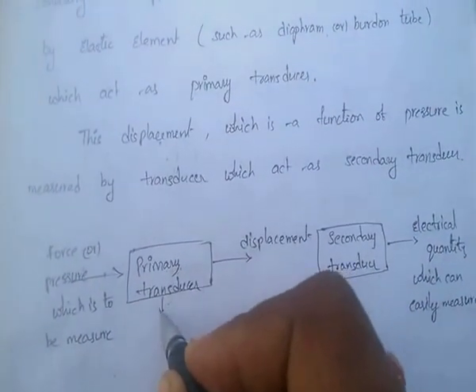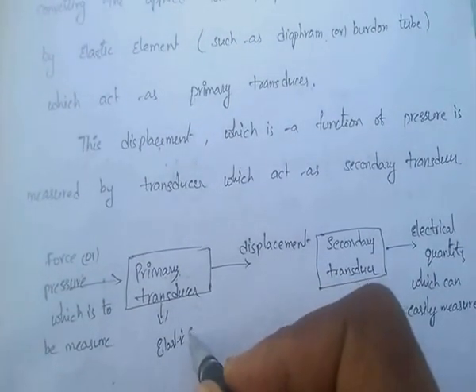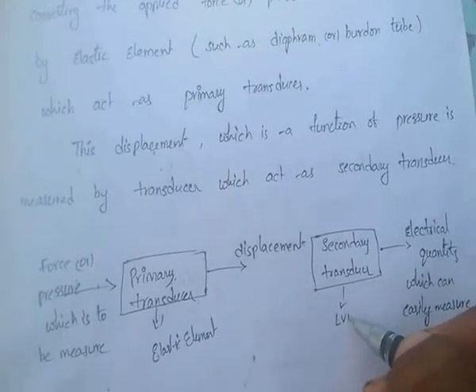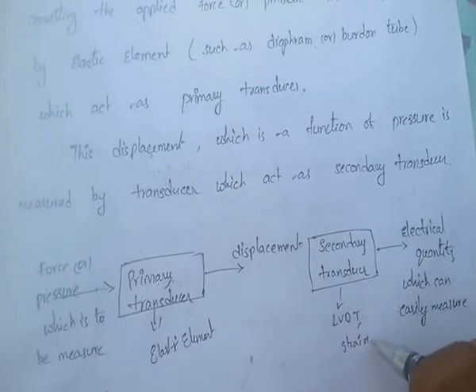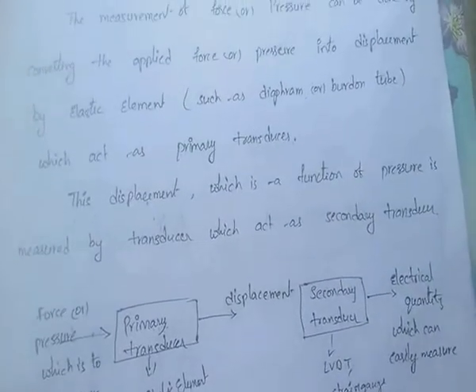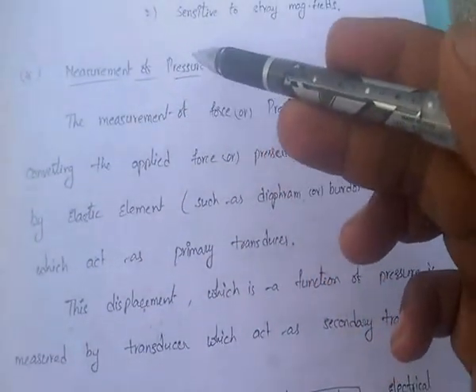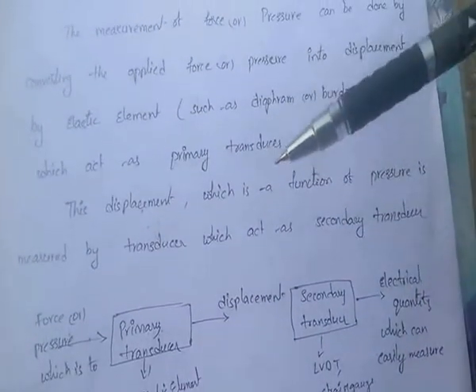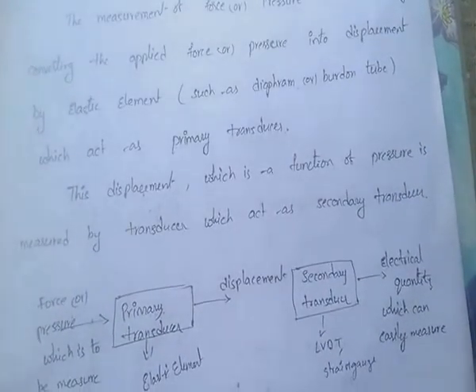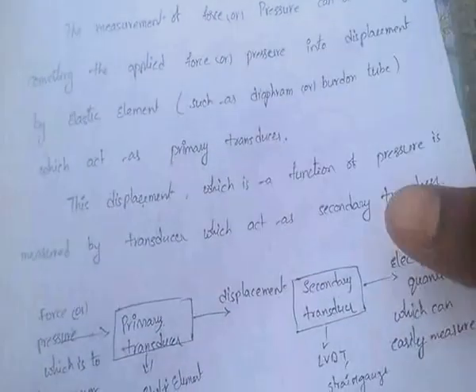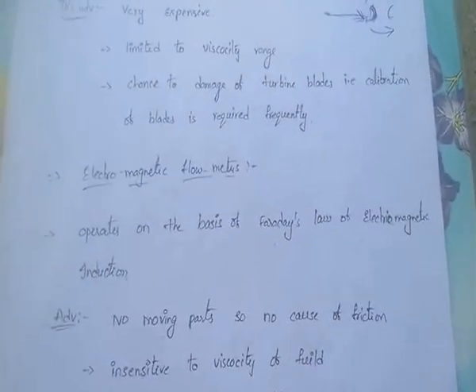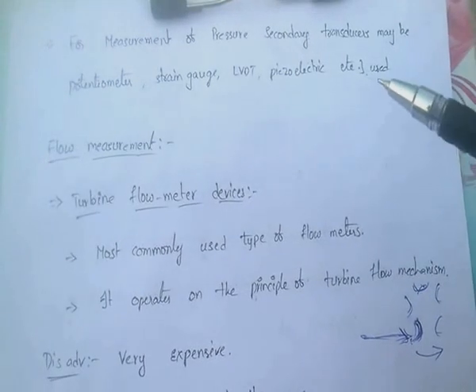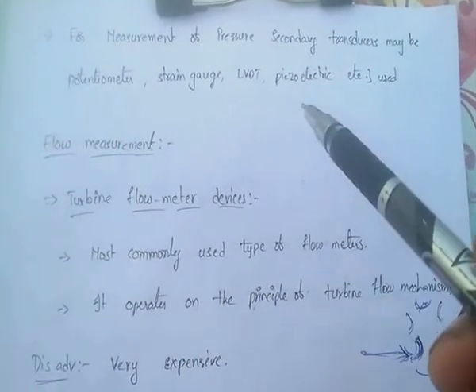The elastic element converts force or pressure into displacement, and that displacement can be easily converted to an electrical quantity by using a secondary transducer. The secondary transducer may be any transducer such as LVDT, strain gauge, potentiometer, or piezoelectric transducer. You can use any of these transducers as the secondary transducer.